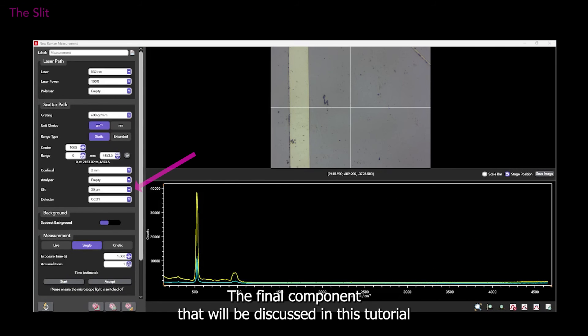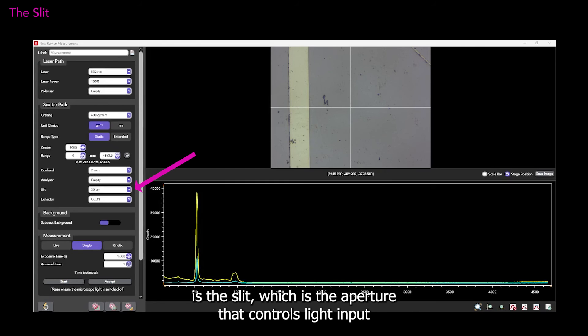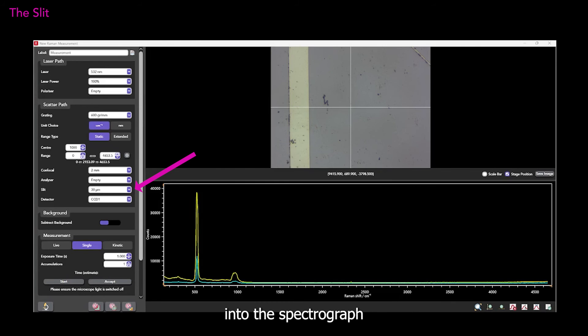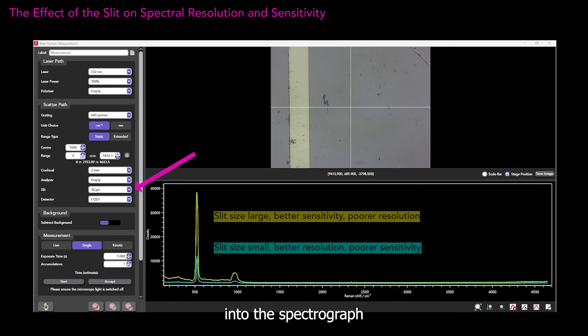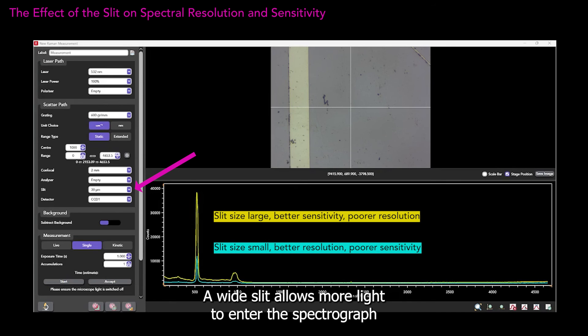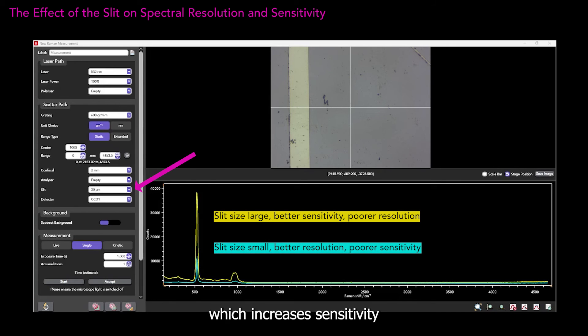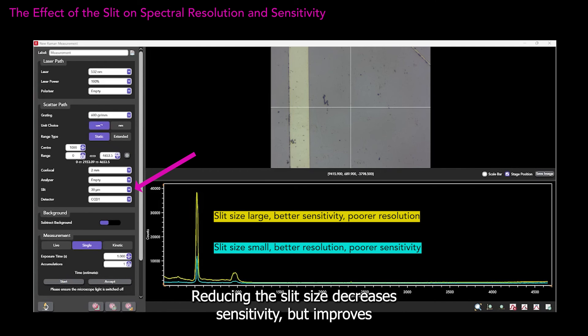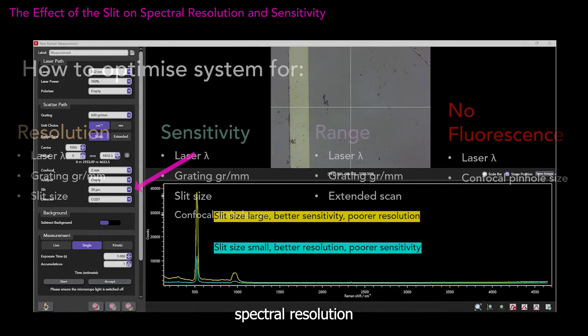The final component discussed in this tutorial is the slit, which is the aperture that controls light input into the spectrograph. A wide slit allows more light to enter the spectrograph, which increases sensitivity. Reducing the slit size decreases sensitivity, but improves spectral resolution.